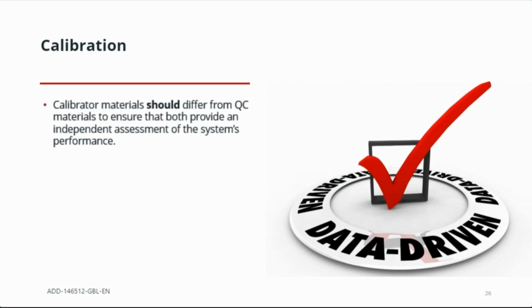An important note regarding calibration. Calibrator materials should differ from QC materials to ensure that both provide an independent assessment of the system's performance. So utilizing just one level of our daily QC is not going to provide that independent assessment to ensure that our system has not shifted from zero bias.